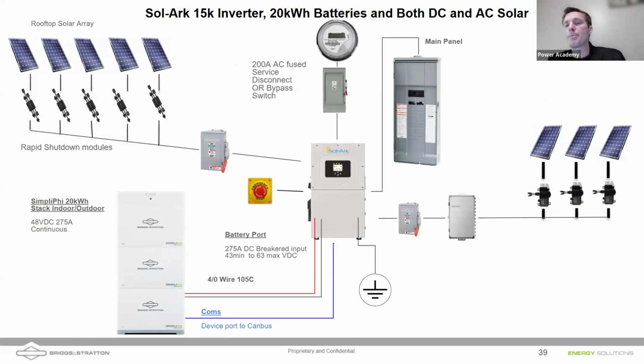It really depends on the type of solar that's there. If you had a grid-tied system and you've got a really old inverter, instead of having maybe Enphase microinverters, let's suppose you have some old SolarEdge inverter. You can either AC couple or DC couple that, meaning you could remove the inverter and just DC couple solar into the Sol-Ark. Or if you want to keep that older inverter, you could bring that in as AC coupled.